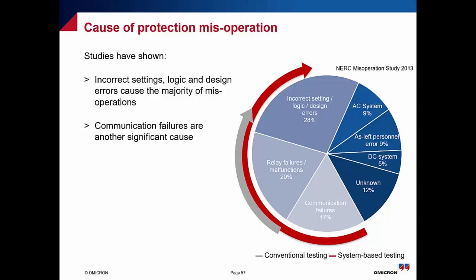still unknown. The good news is that if we do a comparison between the conventional testing, which is the same method which we used, by checking only the parameter settings of the protection relay, and compare that with the new innovative solution of RelaySimTest, which can represent system-based testing, we will find that system-based testing is much more, to add side by side to conventional testing.